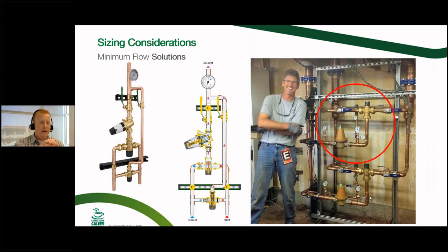Minimum flow requirements. Let me backtrack a little bit, I completely skipped over this. If you're not meeting minimum flow requirements, what's going to happen? What's the bad news here? You are going to get unstable outlet temperatures. And again, we get the phone calls where the guy says, I installed this, I tested it, everything worked great. But if you're not meeting minimum flow requirements, and say that installer is no longer there, you're not going to get enough turbulence inside that valve body to create a good mixture and get a good reading from the thermostatic element, or from the temperature sensor on an electronic mixing valve. That element or sensor is going to see all hot or all cold, and it's going to hunt and bounce all over the place. It's going to be cold, it's going to be hot, and it's going to produce unstable outlet temperatures, which is obviously something you want to avoid.